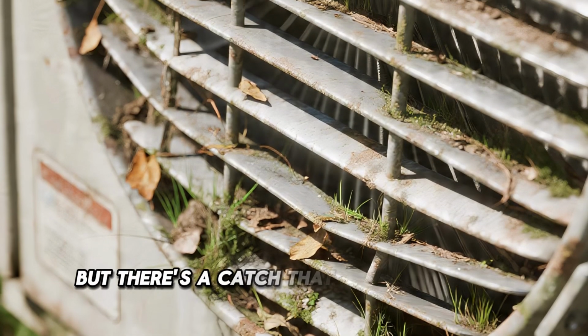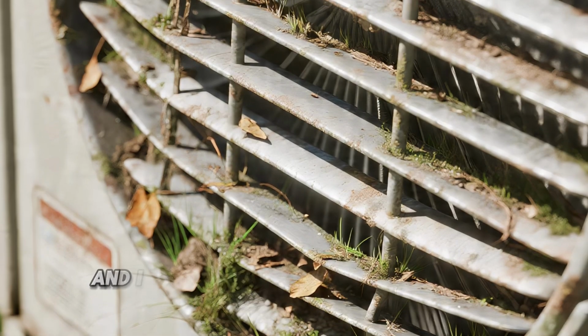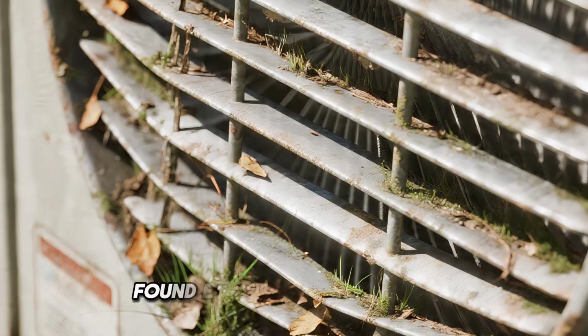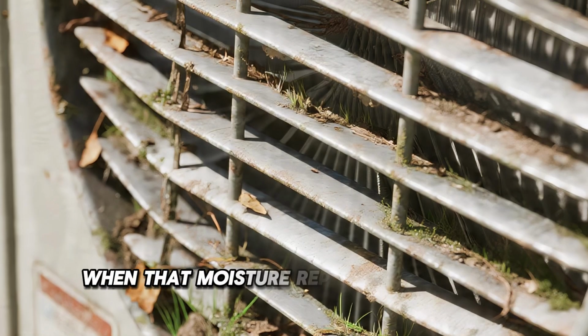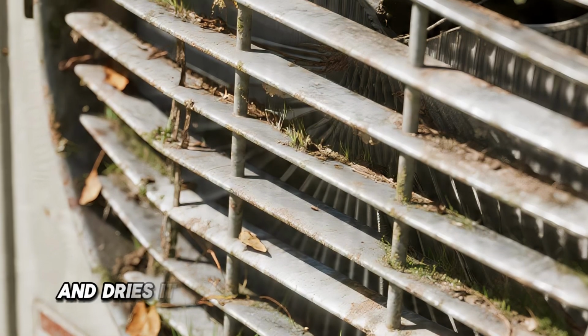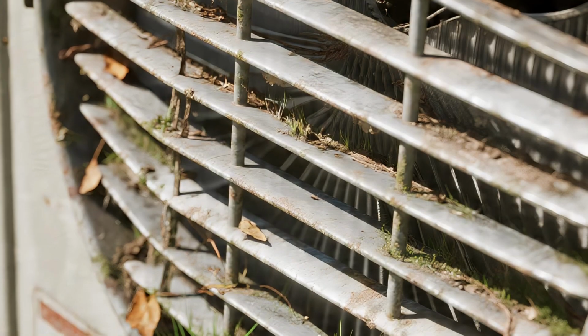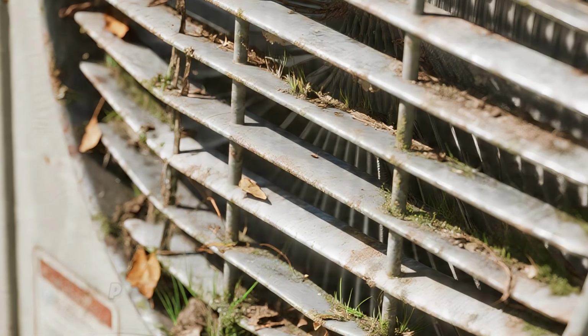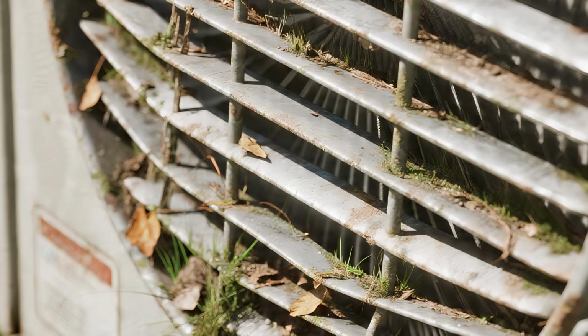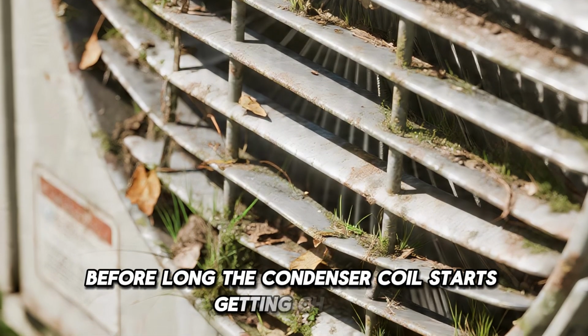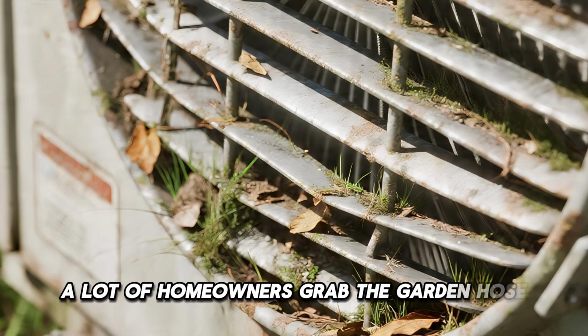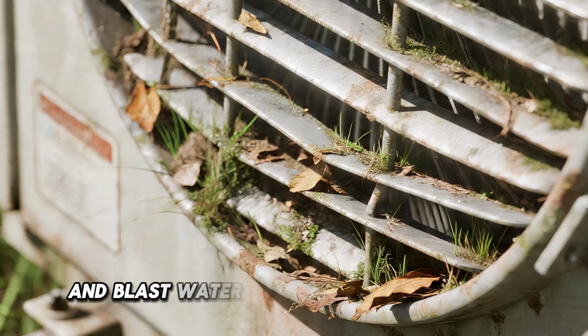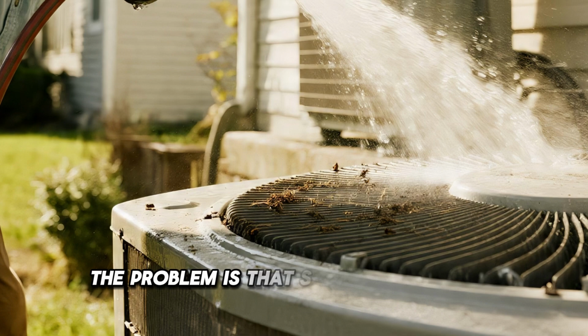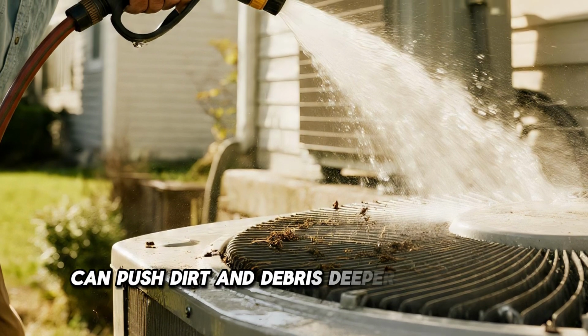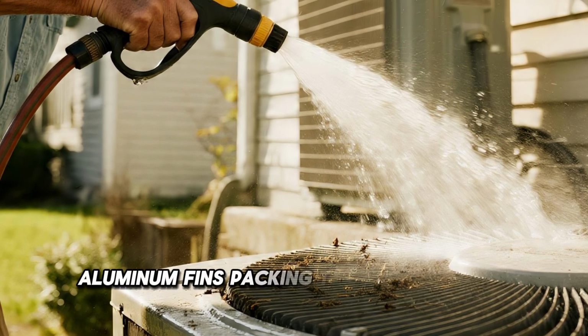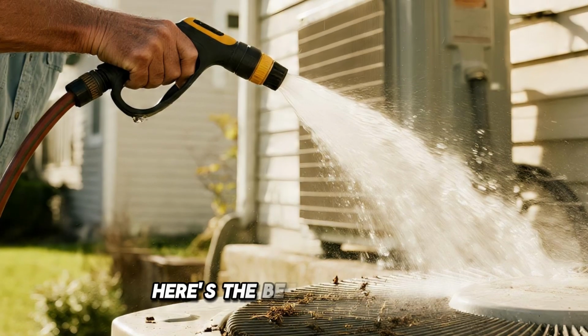But there's a catch. That recycled water can be stagnant, and it may carry the same biological material found elsewhere in the system. When that moisture repeatedly hits hot outdoor fins and dries, it can leave organic residue behind. Now add grass clippings, leaves, pollen, and ordinary outdoor dust. Before long, the condenser coil starts getting choked. A lot of homeowners grab the garden hose, stand outside the unit, and blast water straight through the fins. The problem is that spraying from the outside can push dirt and debris deeper into those delicate aluminum fins, packing the material even tighter. Here's the better approach.